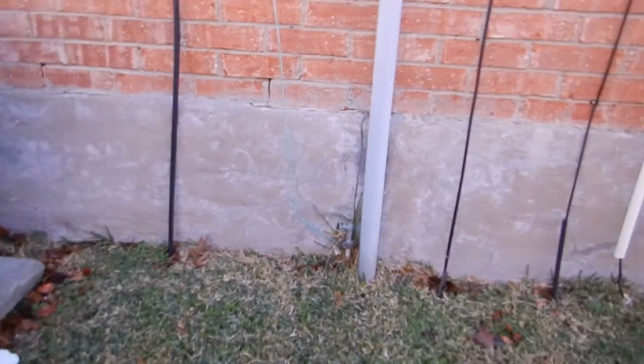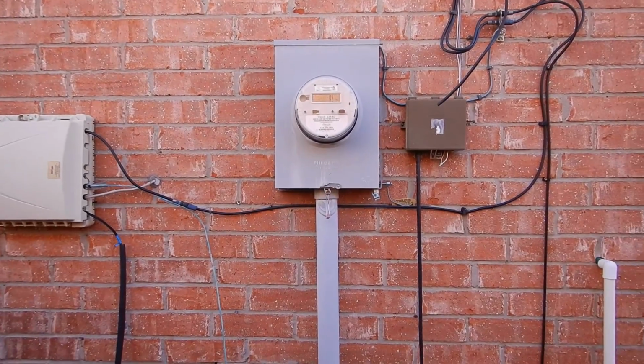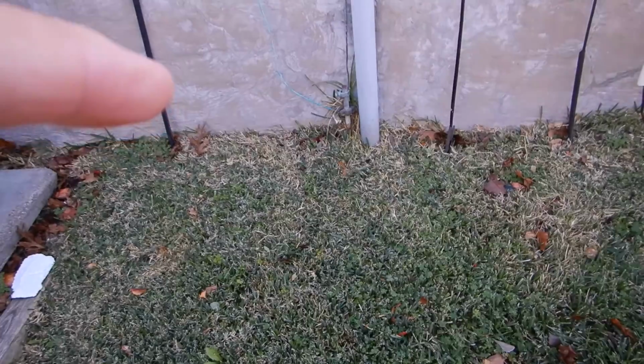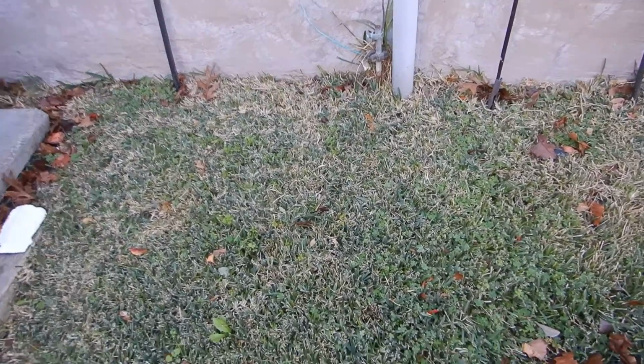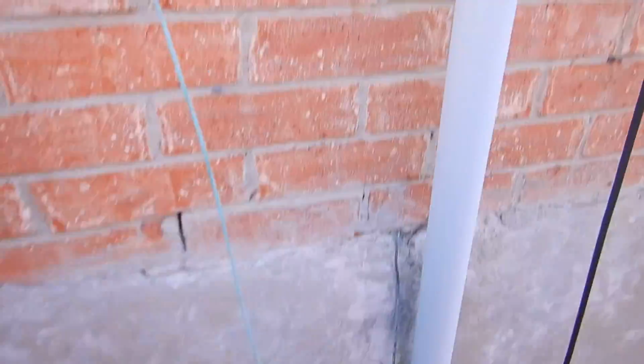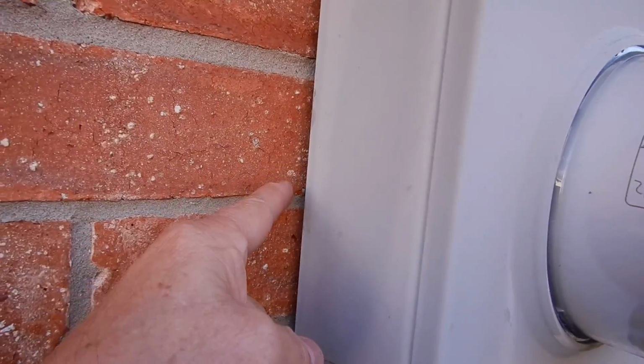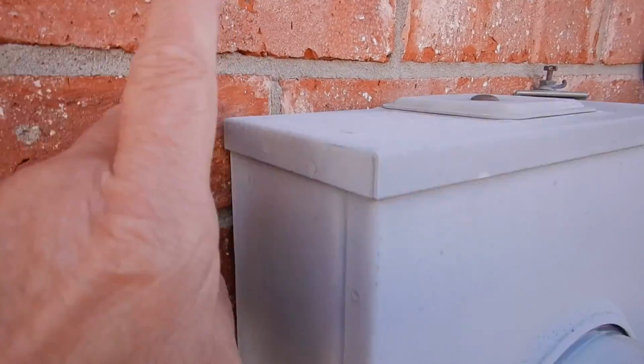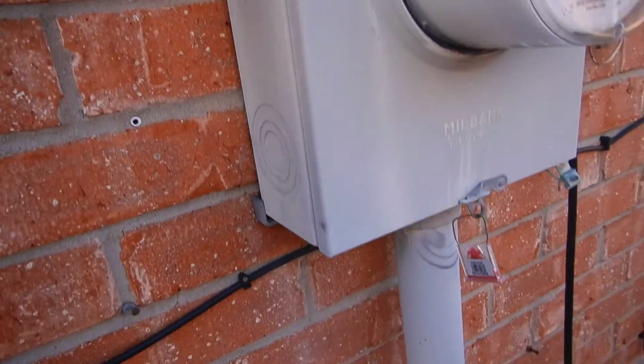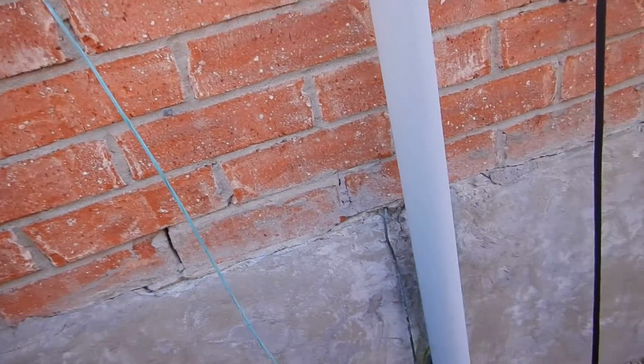Okay, we're on the north side of the garage. This is the electric service, electric meter, and the power is below grade. And what we're noticing here is that this box, the meter box, should be sealed on the sides and the top to help prevent moisture infiltration into the wall system.